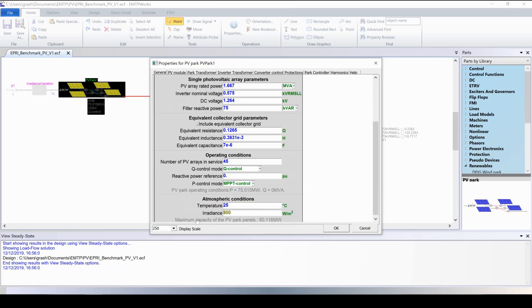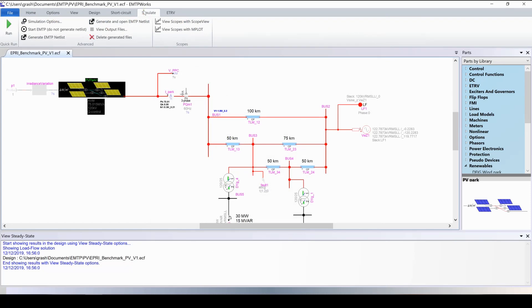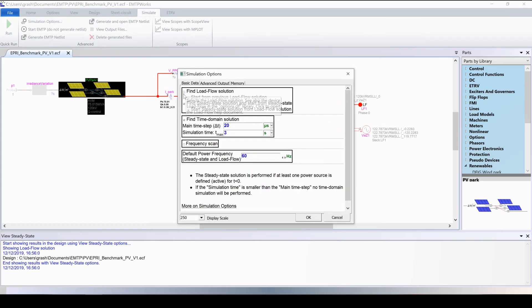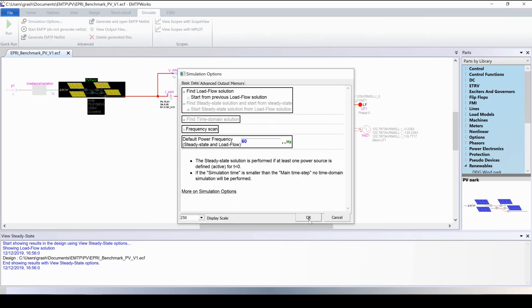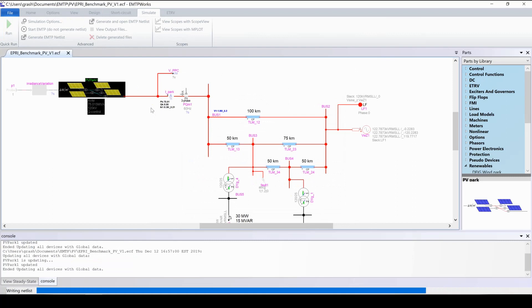We can see that now the MPPT determines the maximum capacity available at 60 MW. Because we change the initial condition, the load flow simulation must be redone. We go to simulate, simulation option, we check find load flow, and run the simulation. We will see that the new power produced by the park with this new value of irradiance will be displayed here.